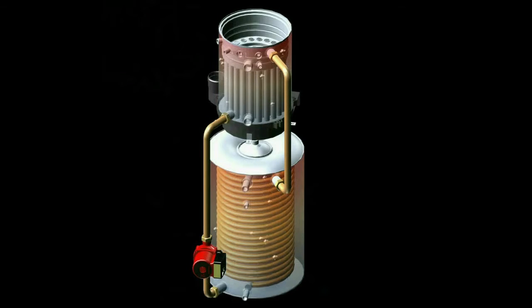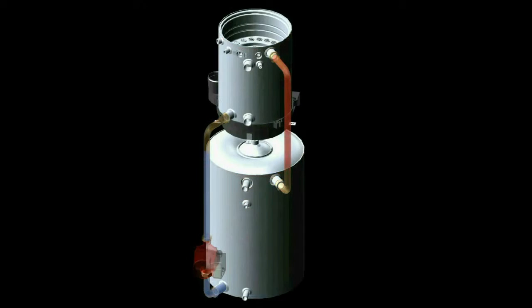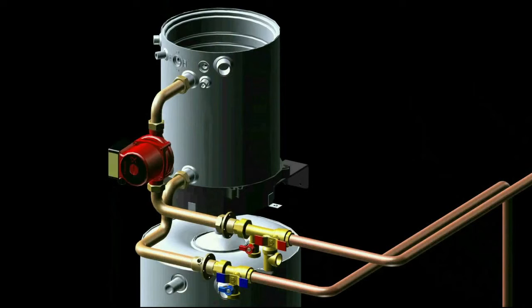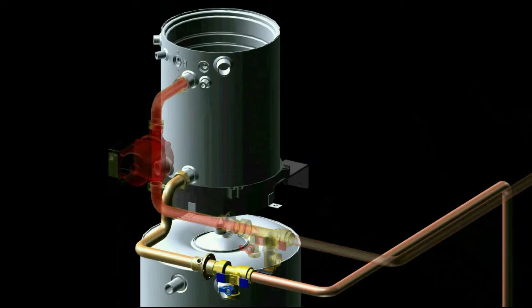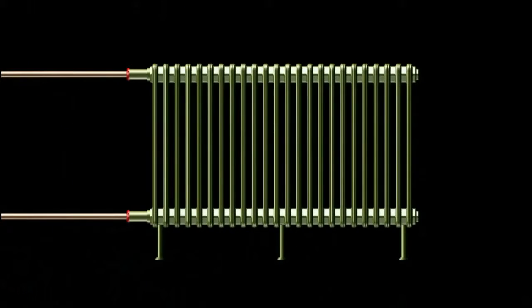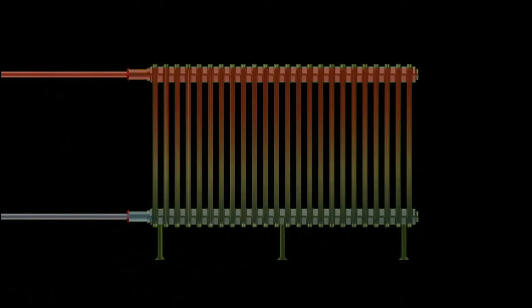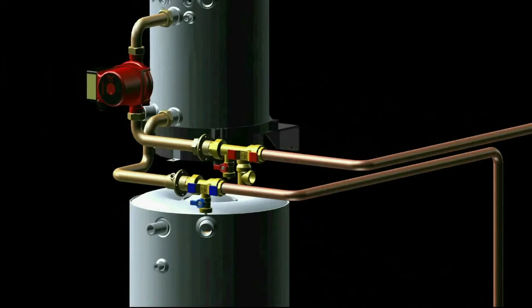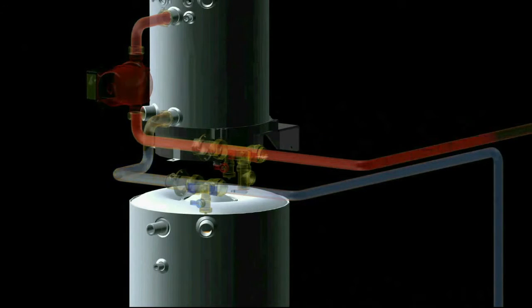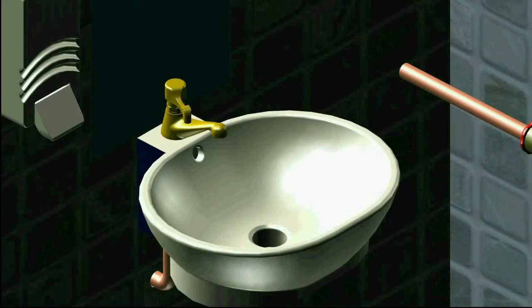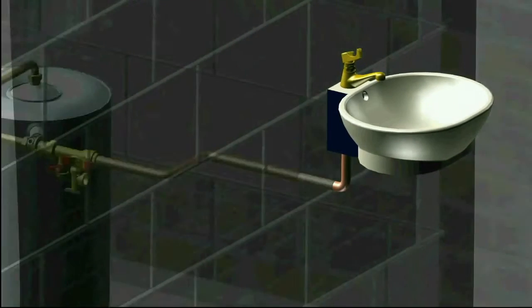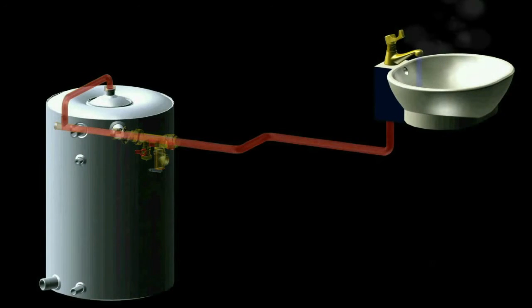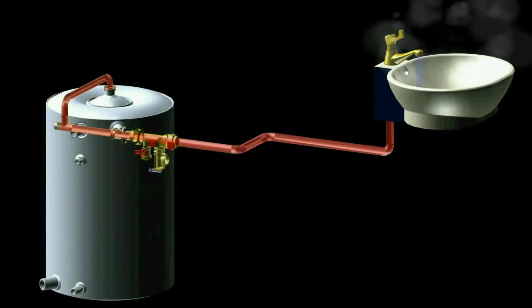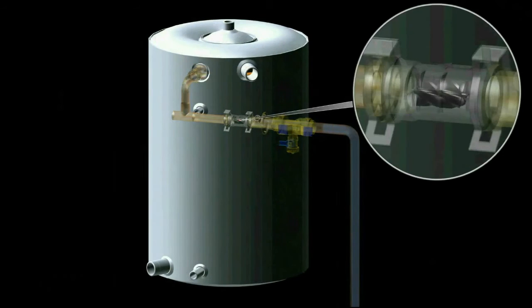After heat is exchanged from the domestic hot water heat exchanger, the cold heated water circulates again to the main heat exchanger. The heating circulation pump operates and heated hot water moves via the heating pipe to the radiator for heating. After heat is exchanged, the heated water returns to the primary heat exchanger for heat exchange. While a consumer uses domestic hot water, central heating is temporarily stopped. Preheated hot water from the heat exchanger is supplied via the hot water pipe to the consumer.